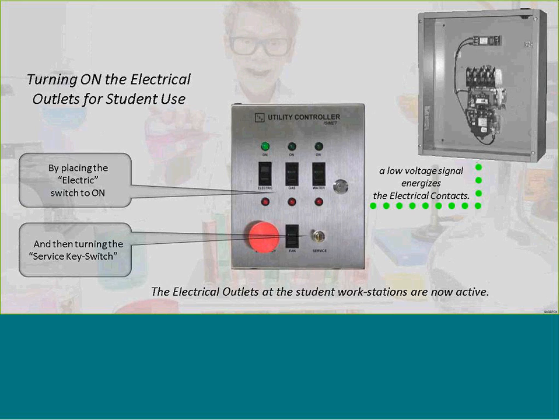Mechanically held contactors are really good, like Square D or Eaton, because you can latch and unlatch those contactors without having to call the facilities people and reset it through a shunt trip.